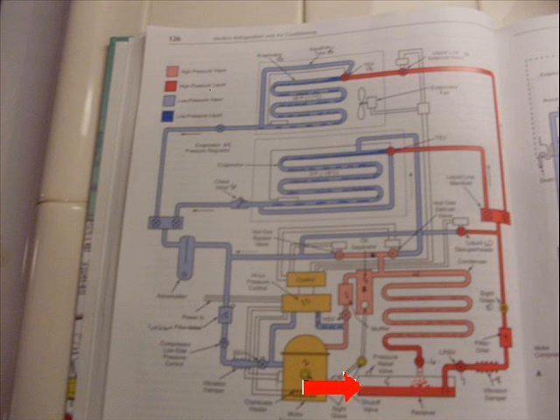Number two, it allows us to shut off all flow of refrigerant leaving the receiver tank. So nothing can leave the receiver tank. Let me call that pump down. And number three, it allows us access for our gauges to take system pressures. Make sure when you do your drawing that the receiver has the king valve firmly attached to it. It's not off in space somewhere.